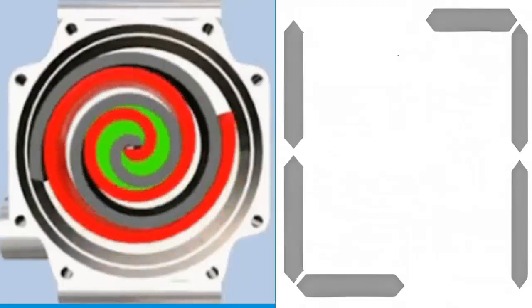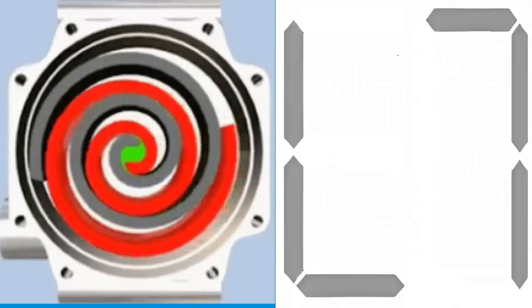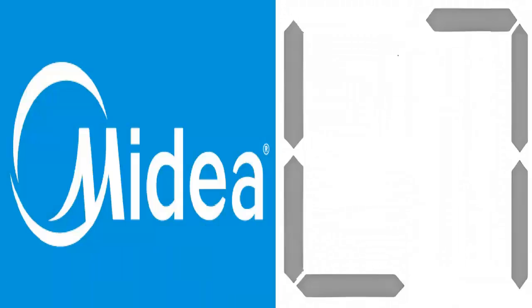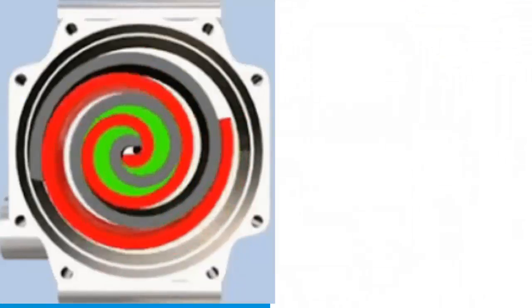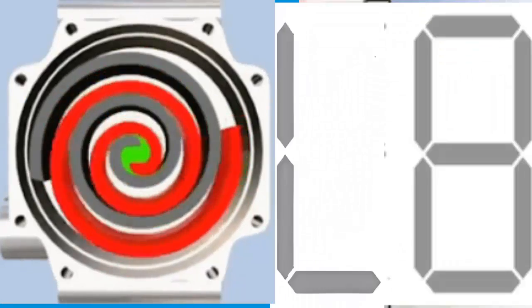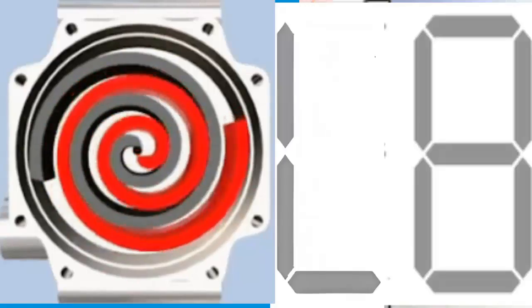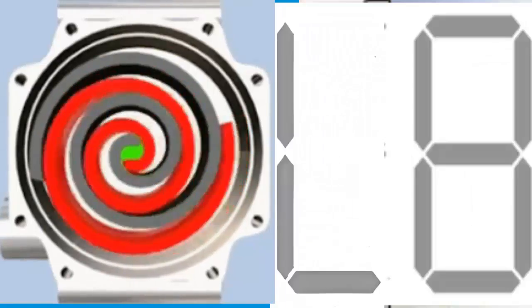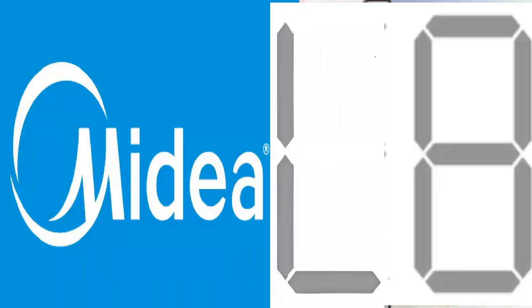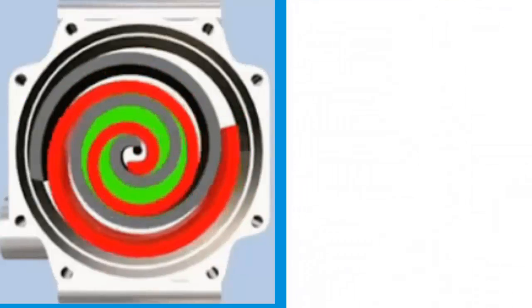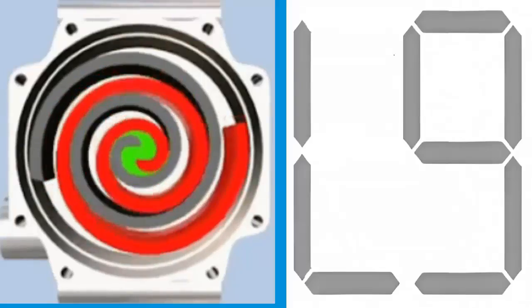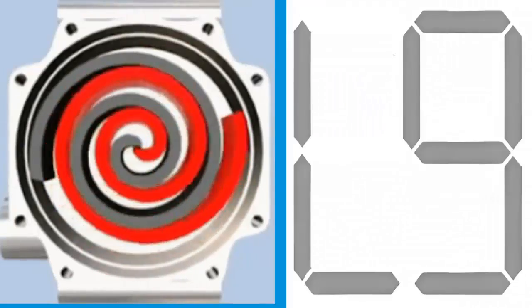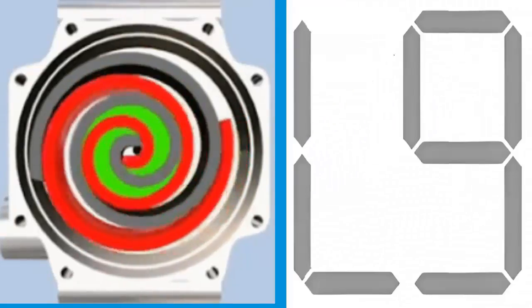The code L7 signifies a problem with the power module's phase sequence. The code L8 indicates a frequency difference after 1 second of more than 15 Hz. The code L9 indicates a frequency difference between the actual and the set frequency greater than 15 Hz.